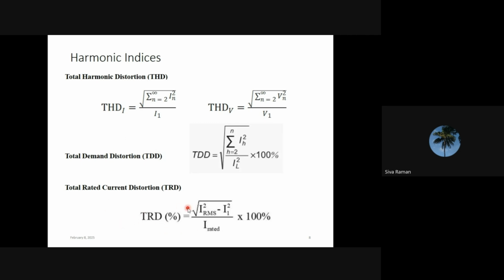In IEEE 519 2022, they have a decision tree. If the customer has an internal load as well as renewable generation, then we have to follow the decision tree. In TRD, we have to evaluate based on the rated current. What is the difference between TDD and TRD? In TDD, we consider the maximum demand average current, but in TRD, we consider the plant capacity rated current. For example, take a 100 megawatt solar plant connected at 110 kV voltage level. For the 100 megawatt plant, what is the rated current at 110 kV? That value we have to consider as I rated to calculate this TRD. So as of now, does anyone have any doubt?